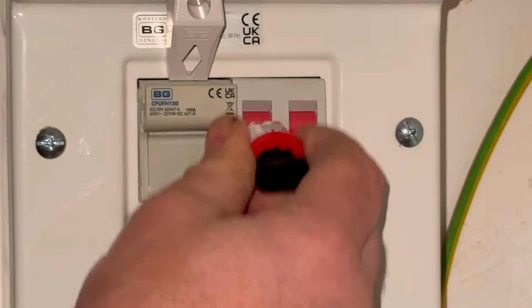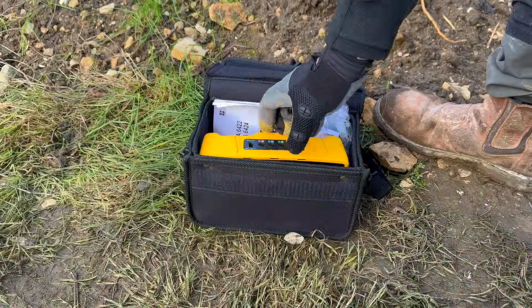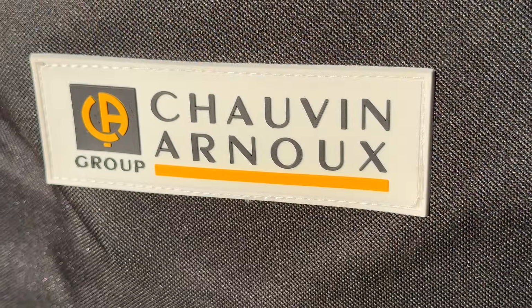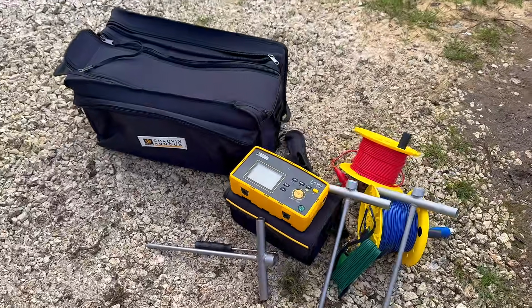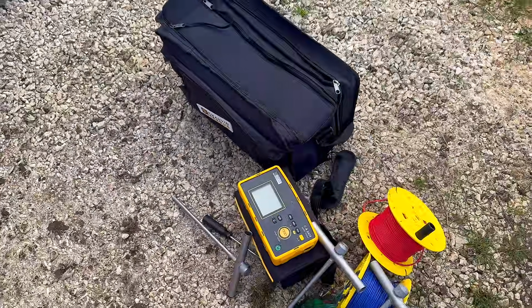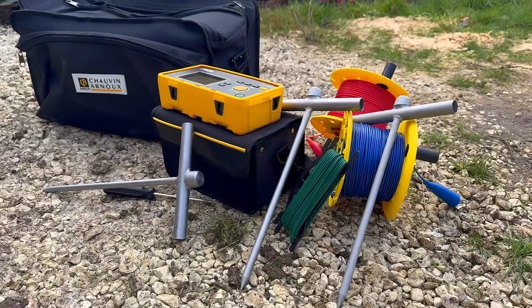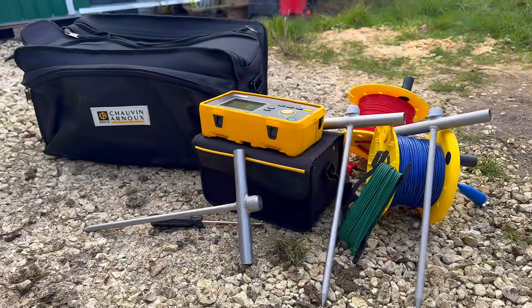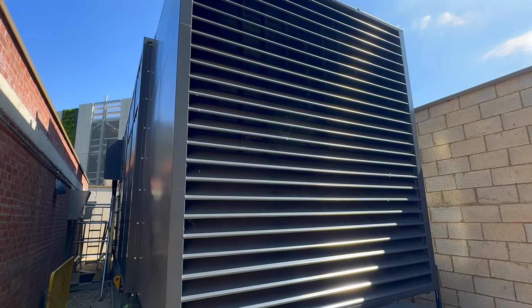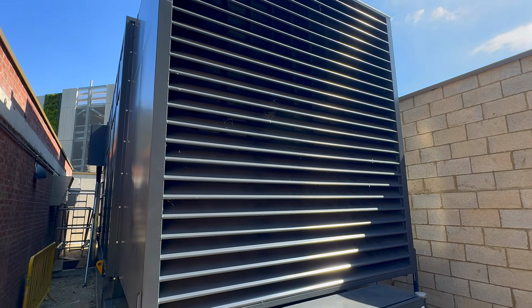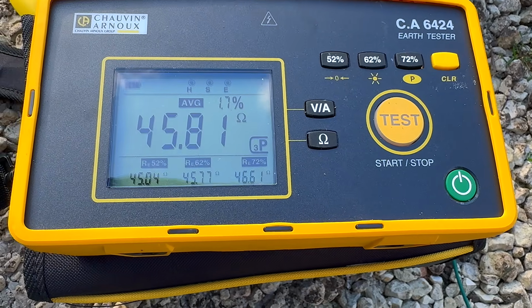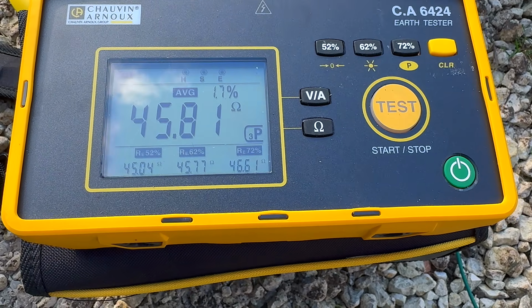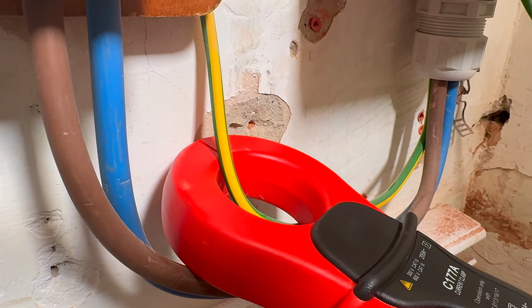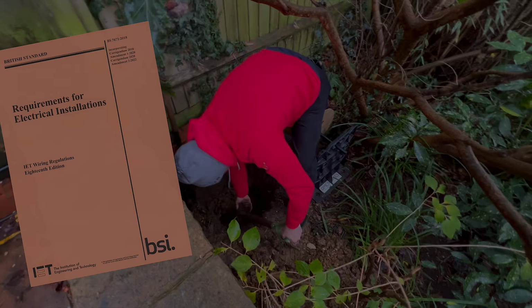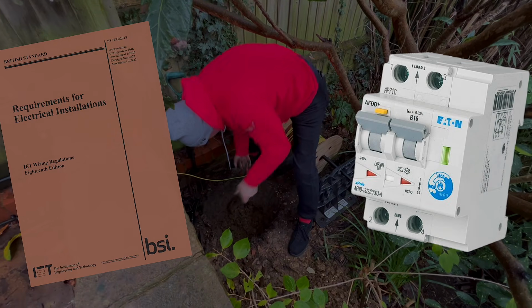But before we test anything, the installation must be made safe. For this test, we're using the CA6424 from Chauvin Arnoux. It can carry out both 2-pole resistance tests and 3-pole earth measurements, even in high resistivity ground. With measurements ranging up to 50 kiloohms, it also allows us to measure voltage up to 600 volts, which is important when working on live sites or shared environments. It makes the probe positioning for the test easy as well, with 52, 62 and 72%, but more on that in a sec. The CA6424 can also measure leakage current from as low as 0.5 milliamps, which becomes important later when we start talking about protection and RCDs.